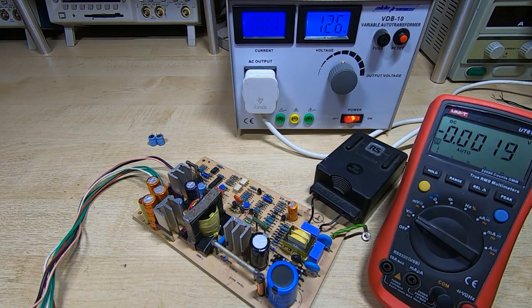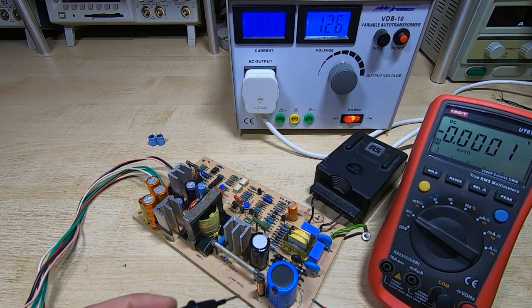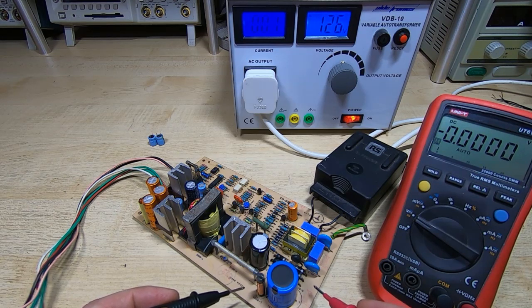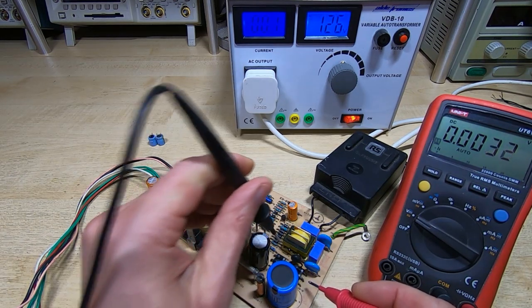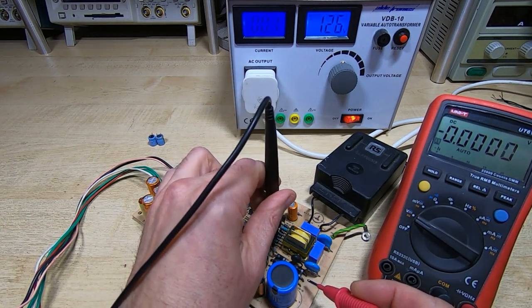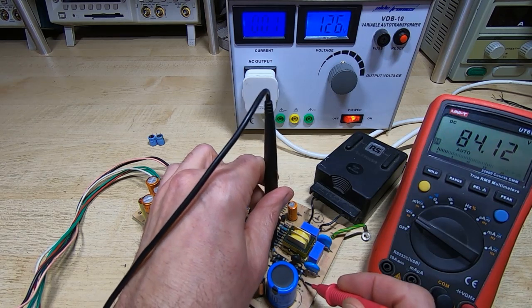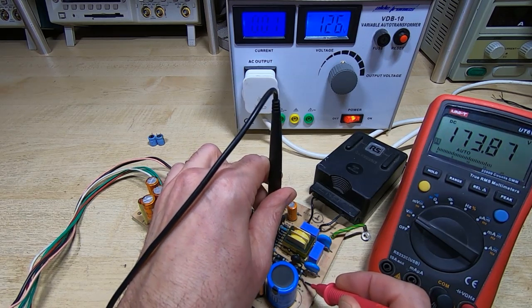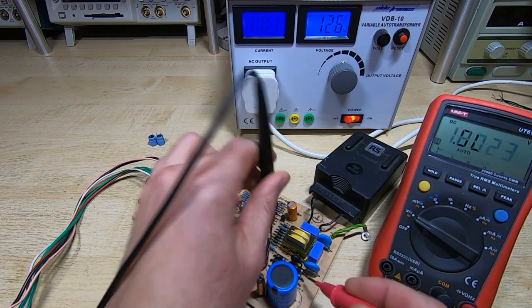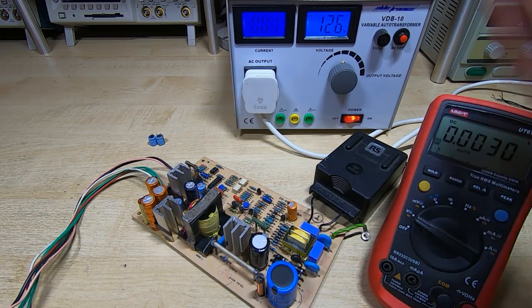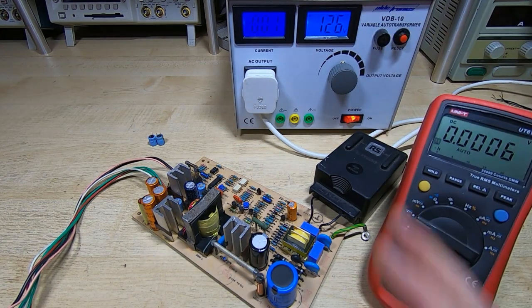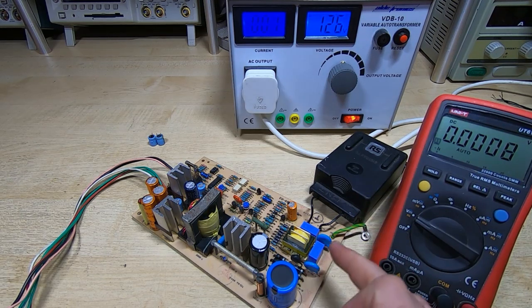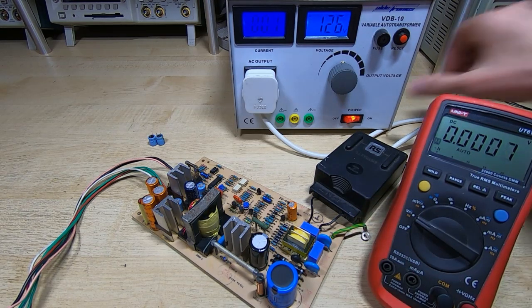So there's nothing on that one, nothing on that one, and nothing on that one. Okay, so no output whatsoever. We can test the voltage output on the main smoothing capacitor and see if we're getting anything there, and we are. So we're getting 175 volts with 126 volts in, so it does look like we are getting the rectified DC.